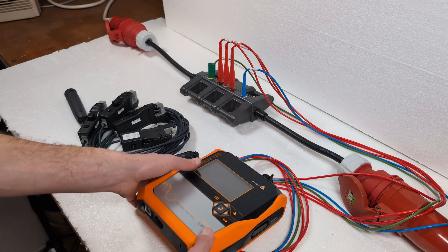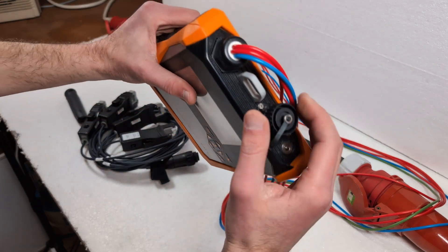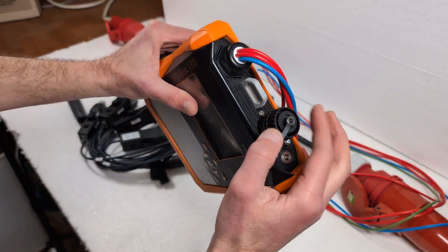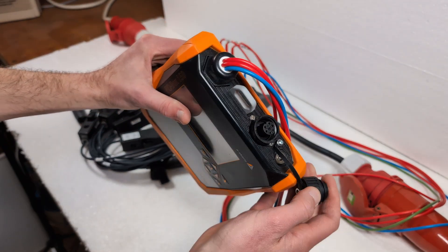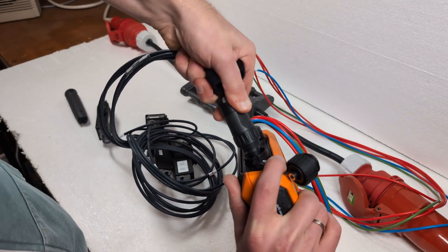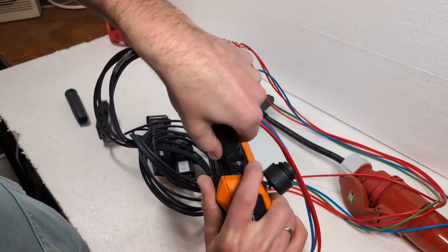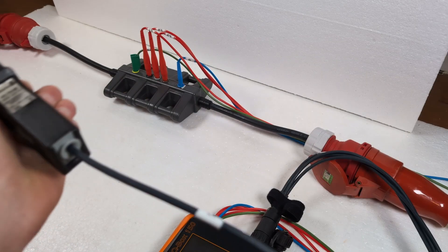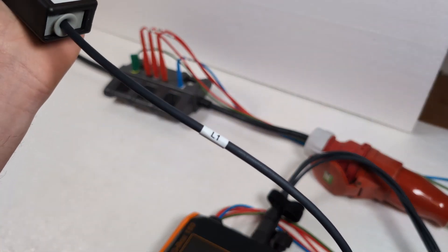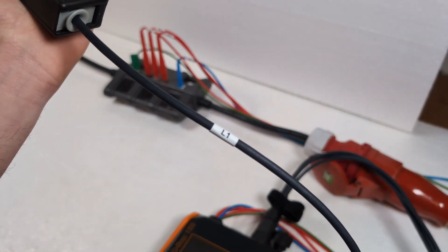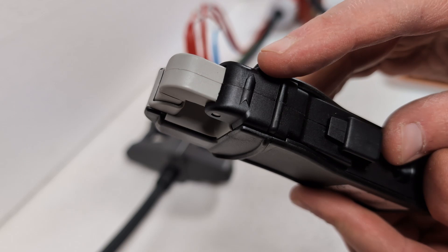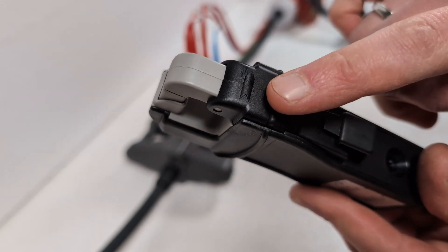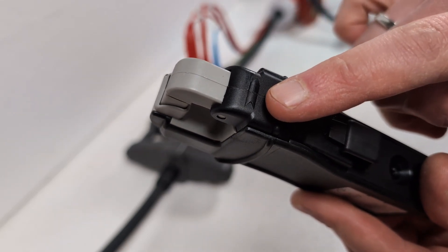Now I connect the current clamps to the PQBox 150. To do this I unscrew the cover and tighten the plug. The current clamps are labeled L1, L2, L3 and N. They are also marked with an arrow for the technical current direction.